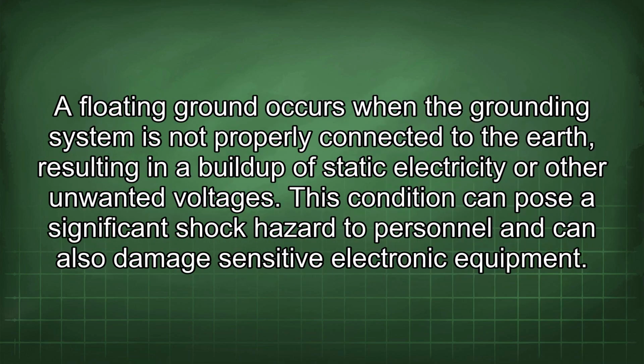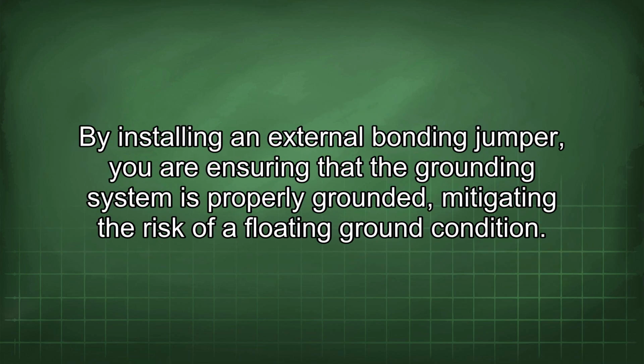A floating ground occurs when the grounding system is not properly connected to the earth, resulting in a buildup of static electricity or other unwanted voltages. This condition can pose a significant shock hazard to personnel and can also damage sensitive electronic equipment.